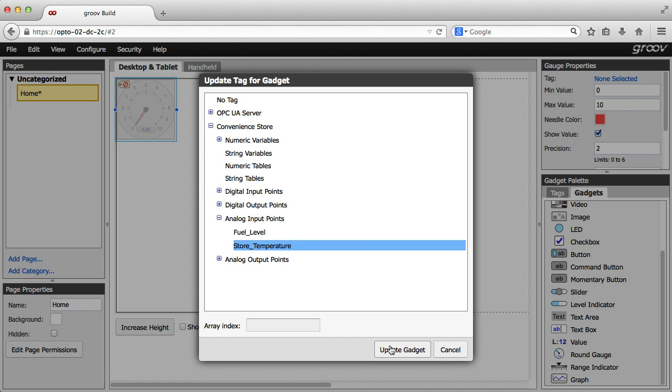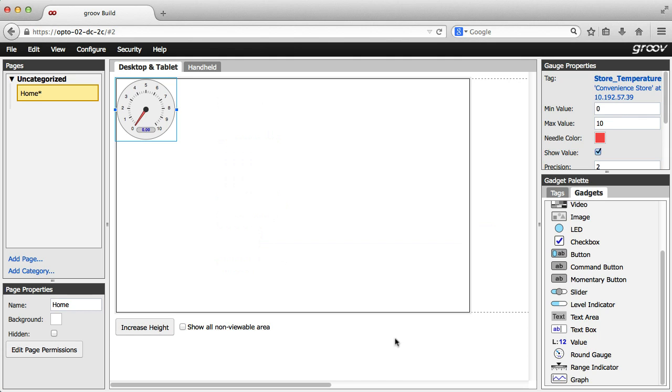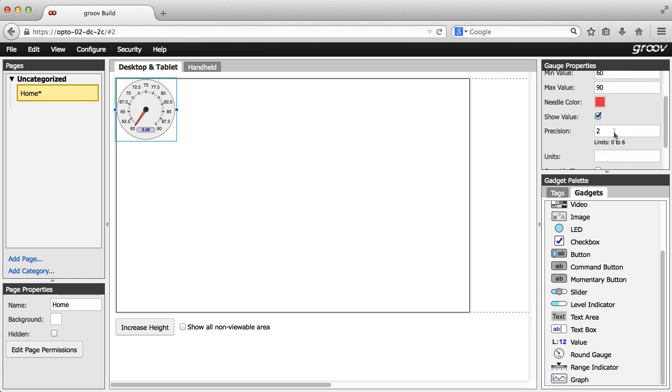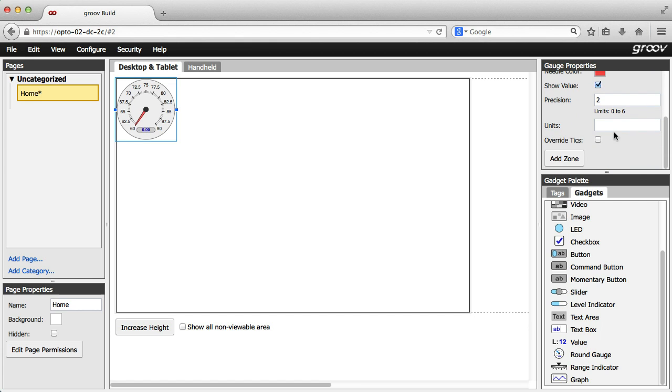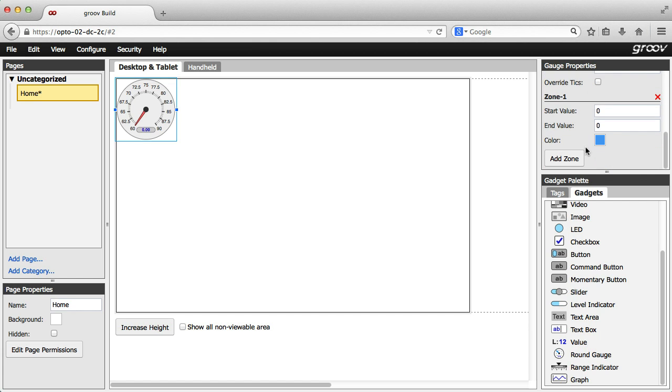I'll select my store temperature here. Then adjust the min and max properties. For this round gauge, let's add an optional red line type zone for when it gets too hot. I'll make the start value 80 degrees and the end value 90 and change the color to red.